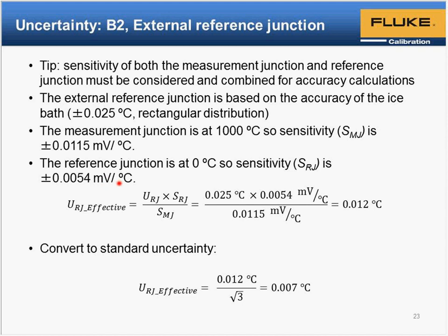Now we plug these two values into the formula. It basically creates a ratio of the reference junction over the measurement junction sensitivity, and we multiply that ratio times the entire reference junction bath or ice bath uncertainty. So our 0.025 degree reference junction uncertainty becomes 0.012 degrees C.